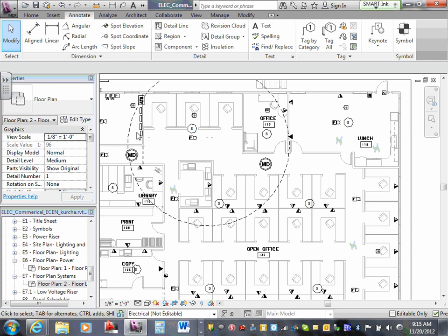And when you get into battery sizing for your fire alarm panel, because you need to have a battery backup for your fire alarm panel, obviously the larger the candela, the more battery you need, because it takes more power. So that's another thing, depending on how detailed you get into sizing everything, you need to size your batteries too.